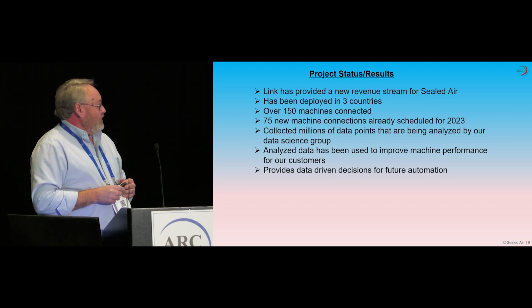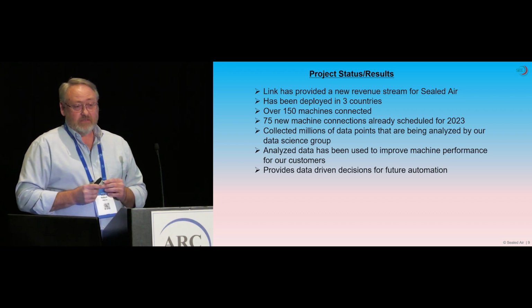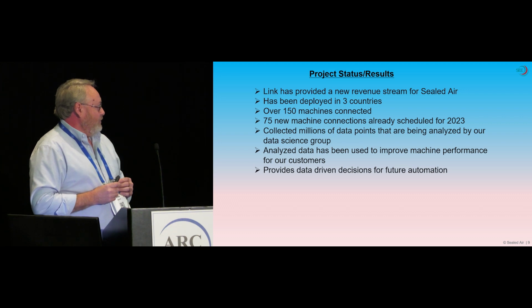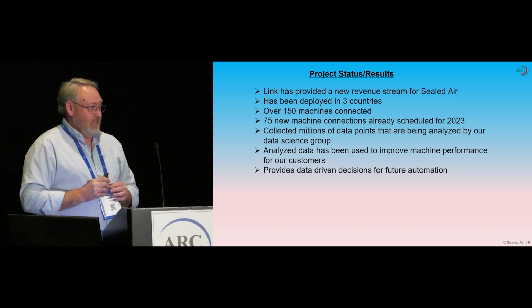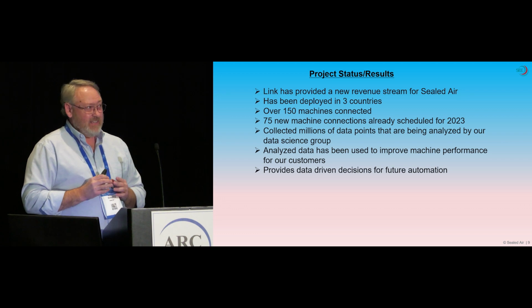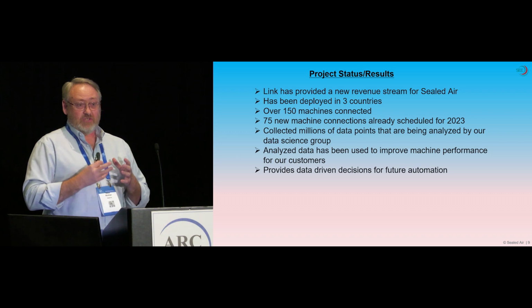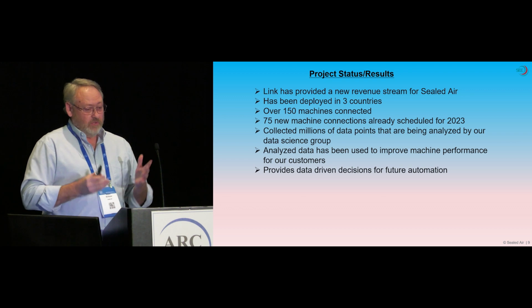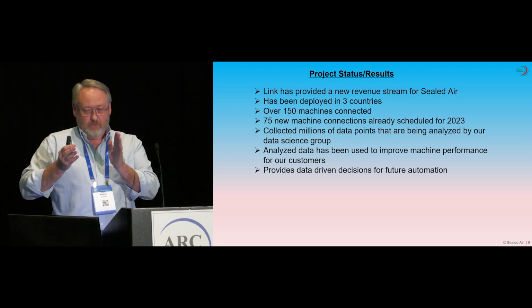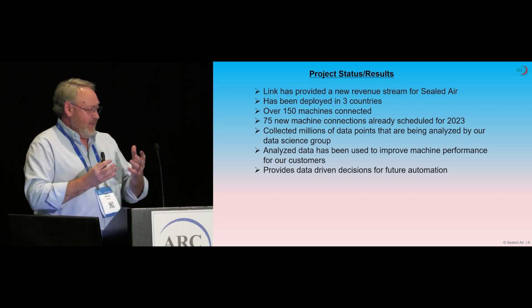So far we've been deployed in 3 countries. We have over 150 machines connected, and when they're connected, it's connected permanently. We're sending data continuously. Every machine cycle, data's pumping through. We're getting machine statuses, like I said, alarms, machine modes. We know key parameters for every machine cycle that we're able to capture on a machine cycle trigger. So we'll know this particular package was made with this vacuum level, this seal current, and this seal voltage. We can package that up.